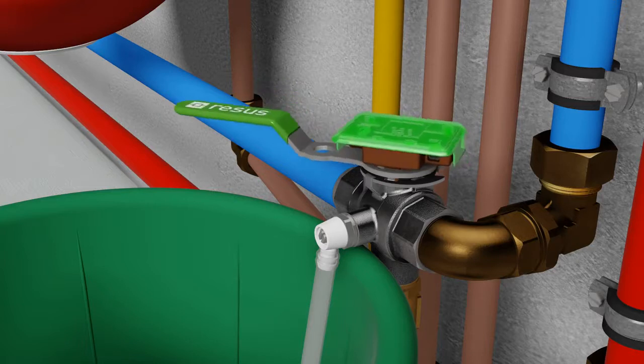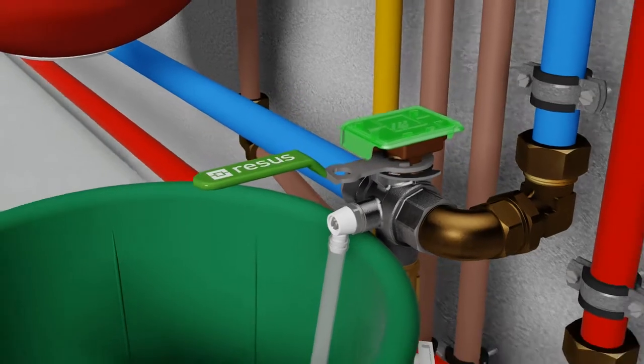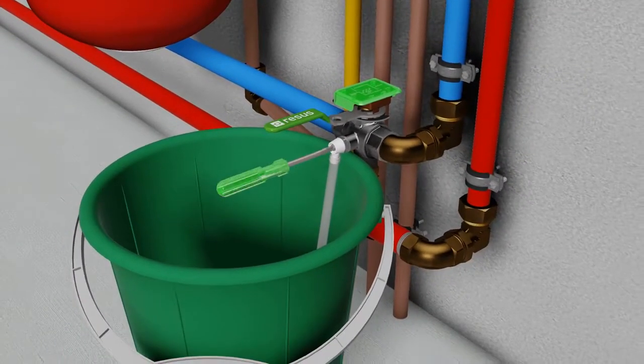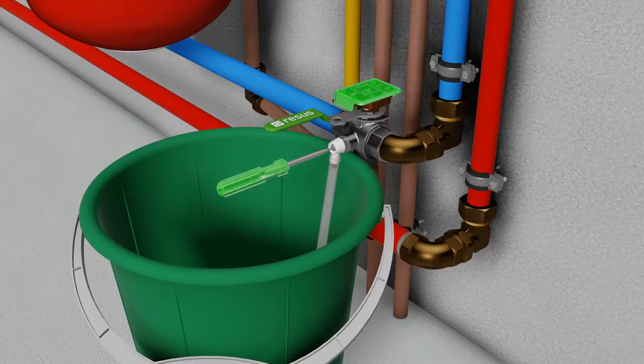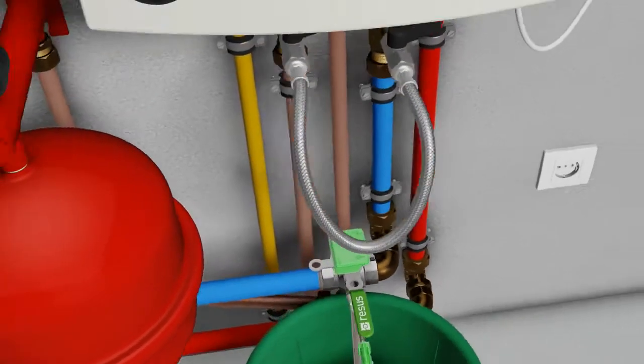Closing the valve isolates the expansion vessel from the system so that now it can safely be drained. Once all the water is out, the pressure on that side has come to zero.